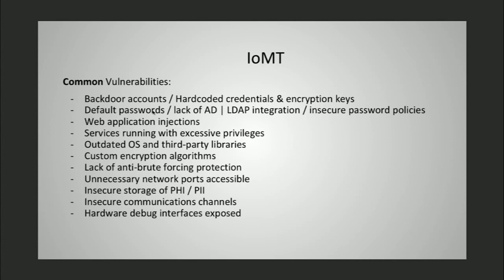Patching is a really big problem because with medical devices, by the time they reach the market, they usually have to go through FDA approval, which means that they usually come outdated, and because you cannot just apply patches on an infusion pump, let's say, without first going through a lot of rigorous testing, the whole patch management is a big problem.